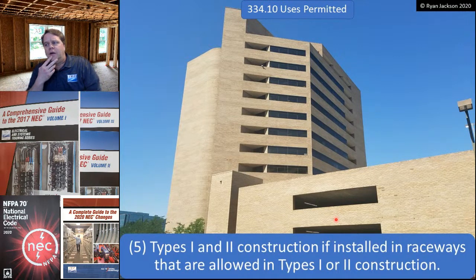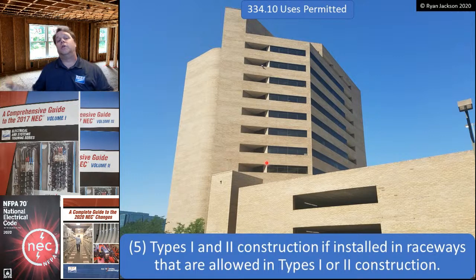You can put NM cable in types 1 and 2 construction, a high-rise commercial building, if you install it in a raceway. So you're going to pipe your whole building with EMT, and then you can pull NM cable through it. Got it. Yeah, okay, we'll allow you to do that, but I think we can agree that's a bit absurd.